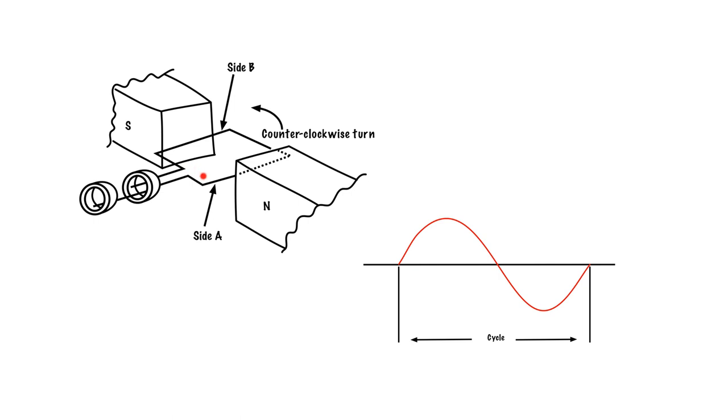So for the first 180 degrees, as A goes up and rotates all the way here, it starts at this point, goes up, goes down. Then as A kind of shifts around it goes the opposite direction underneath and back up. It goes up in the opposite direction and down again. So what we see is in a full 360 degrees of mechanical rotation we create one complete sine wave. Now if I time that and have this happen, so let's say that this side here, A, goes all the way around in 360 degrees mechanical rotation and it does that in one second, we create one sine wave in one second, therefore we get one hertz or one cycle per second.